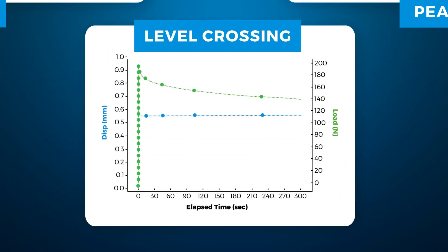Level crossing data type is used for stress relaxation or creep tests, in which the collection of each data point is triggered by a user-defined data change of a specific channel, resulting in data collection at a high sampling rate at the beginning of the test, but less and less data points as the sample relaxes or creeps and approaches equilibrium.